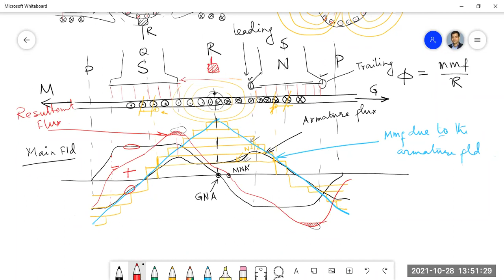Okay, another thing is that initially the geometric neutral axis had a zero flux value, and therefore we generally place our brush where we have the zero flux value. Look at the figure, where the brushes are placed, at P and R, isn't it? In the previous figure you just tally with this. So P and R having the brush position, because generally we place, I will discuss that later, because that is related to the commutation. When I discuss the commutation, I will discuss that in detail. But generally we prefer to place the brush at the point where the flux becomes zero, to avoid the sparking.